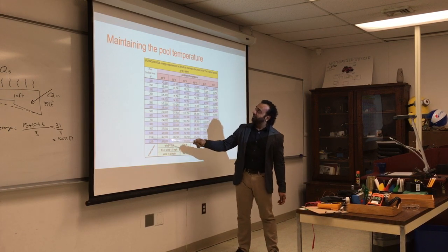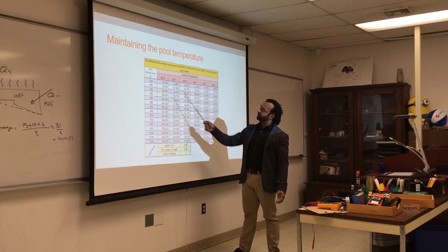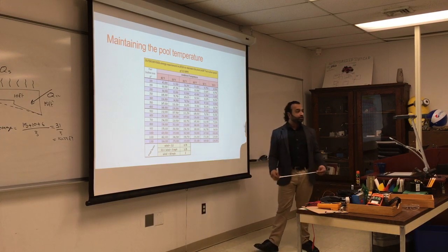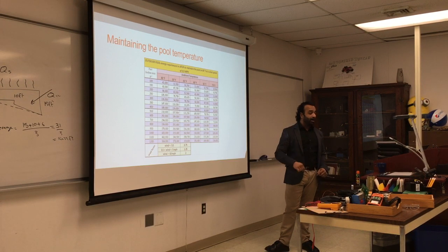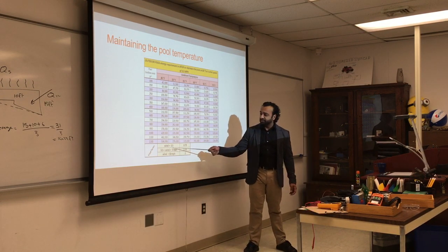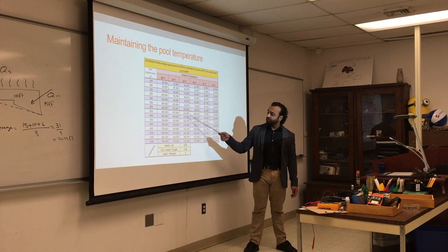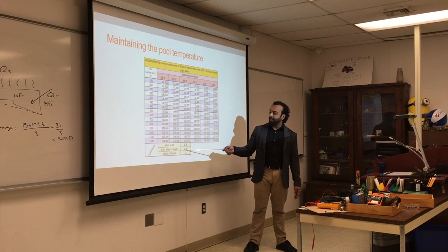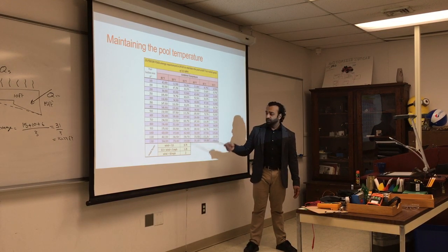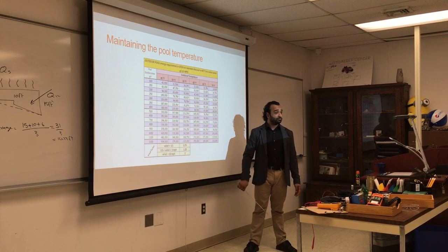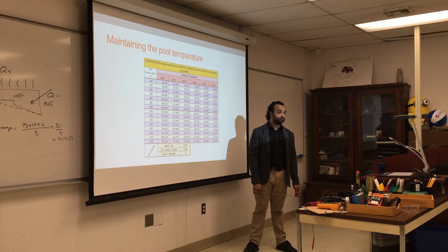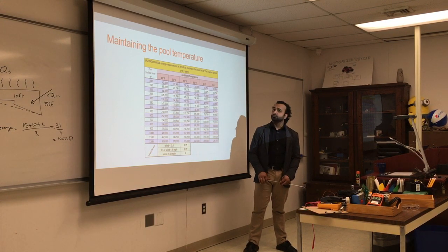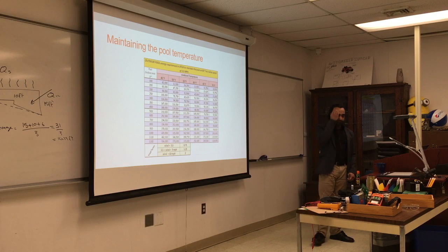And now we're going with the surface area. And what is the ambient temperature, from 40 to 70? How much will we need to keep that pool hot? And this is the wind factor. If you have less than 3.5, then you multiply whatever you got here by 0.75, which is a little bit less. Between 3.5 and 5, you multiply by 1.25. More than 10 miles per hour, you're gonna multiply by 2. And again, this is a ballpark, and it should kind of give you an estimation of how much heat you need.